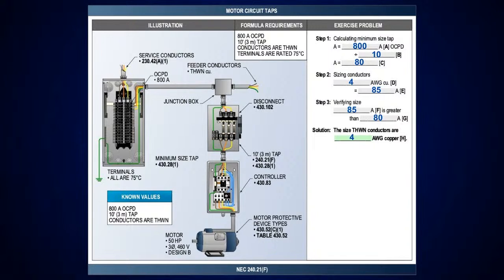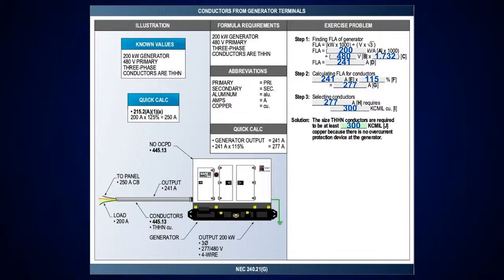Now, if I go over and I look at table 310.16, I come down and pick up my 75 degree C column. The next size above that's 85 amps, which is a number 4 conductor. So therefore, the size conductors required are a number 4 copper. But if you notice, did I change anything that I've said up to this point about doing a tap? No. Kept it all the same. Did not do one thing different.